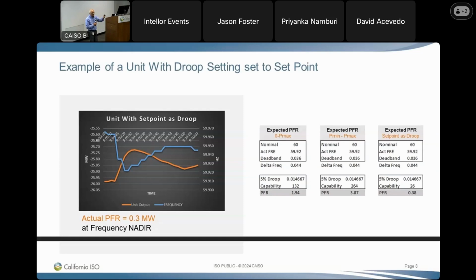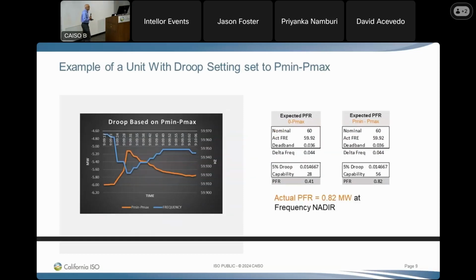And it's that easy for us to be able to tell. So you're not going to get away with it. Once the frequency event happens, we look and we'll find out and we'll come out. So do it right from the beginning if you're involved and engaged with a battery storage project right now. And this one is an example of a droop setting from 0 to Pmax, which we love. I mean, Pmin to Pmax, I should say. And you can, again, see how easy it is to do the calculation and figure out where the droop setting on that unit is right now.